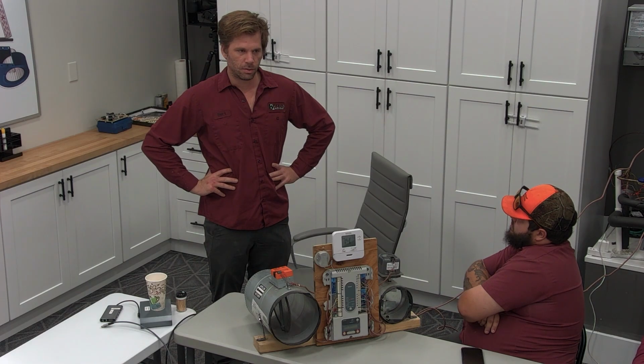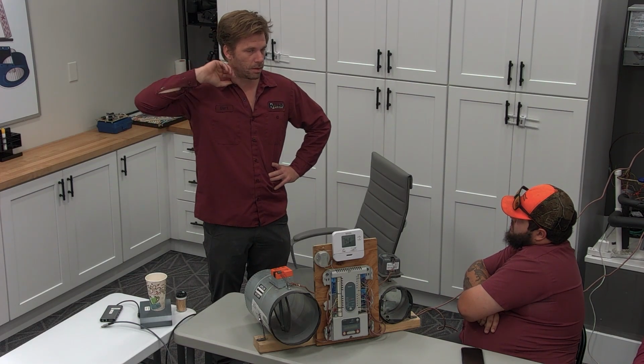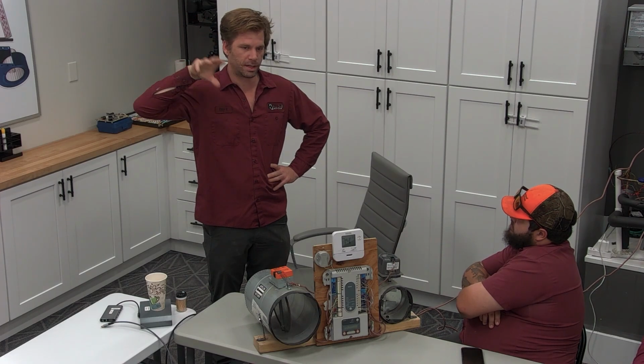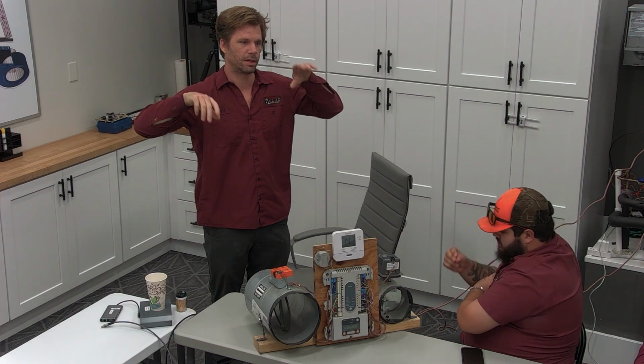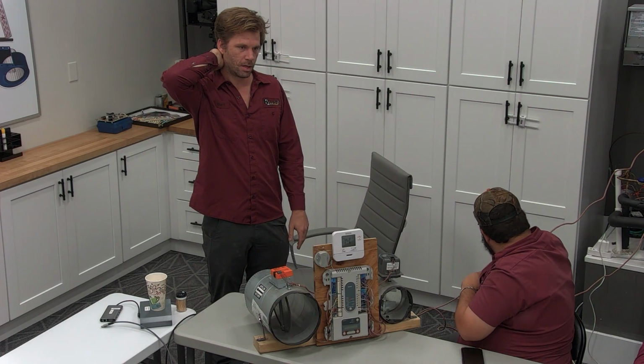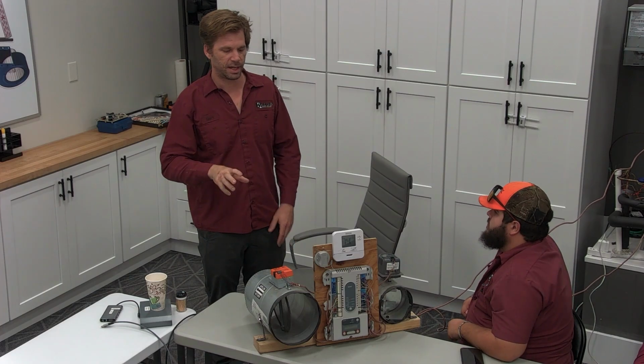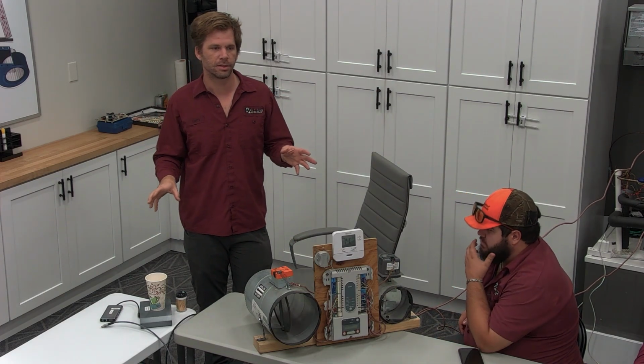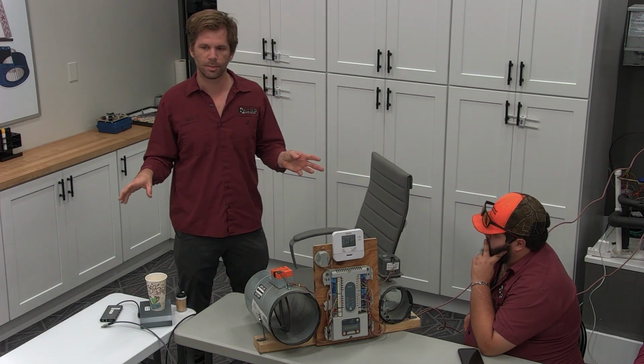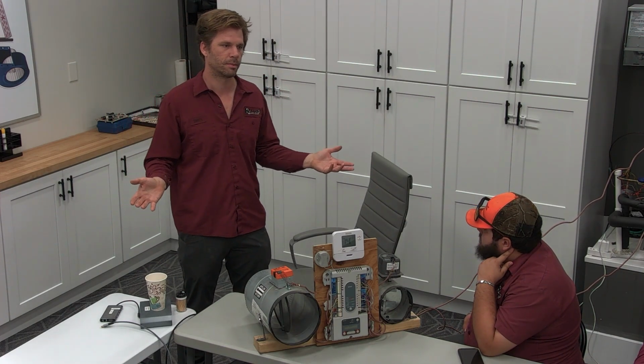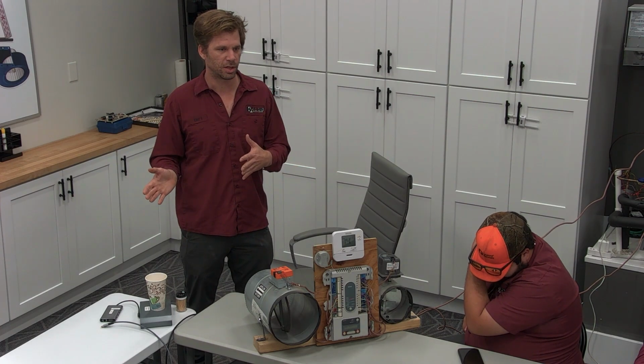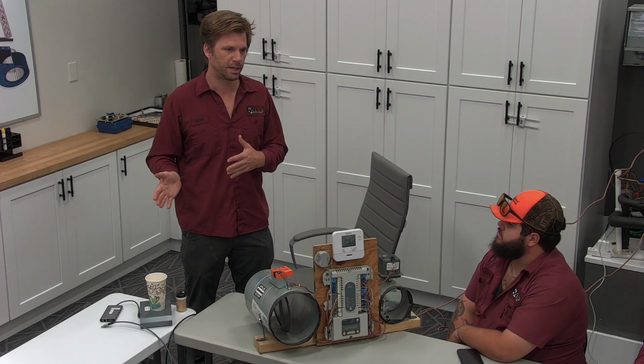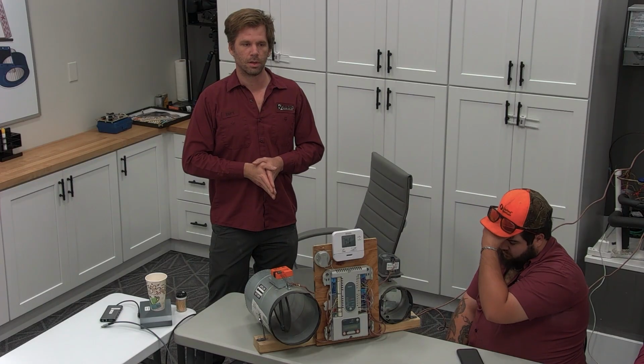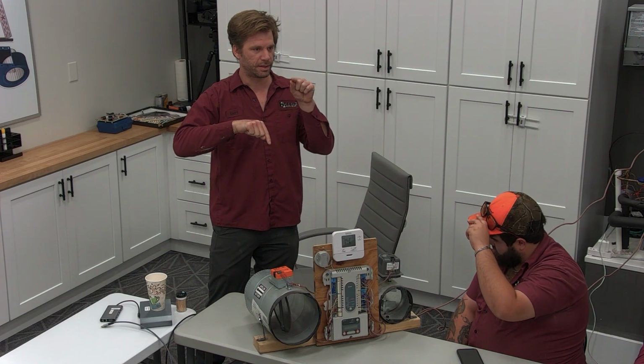Another confirmation that you should do on a damper system is to turn all the zones on and then turn them off one at a time. So while the other zones are running, you turn one zone off and you confirm airflow stops in that area. It's really common to have a thermostat tied into the wrong motor, and it takes just the right scenario to notice. A lot of times in the summer, multiple zones are calling at the same time, so you may not notice. And every once in a while, when one should be shutting off, it stays on a little longer than it should and overcools the space, or when one should be calling, it doesn't call until the other zone gets hot and calls.